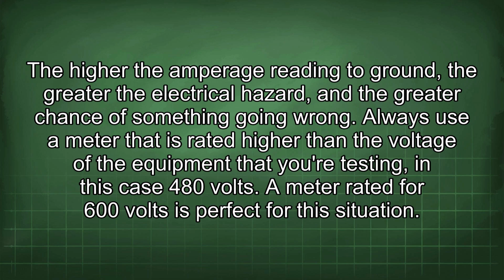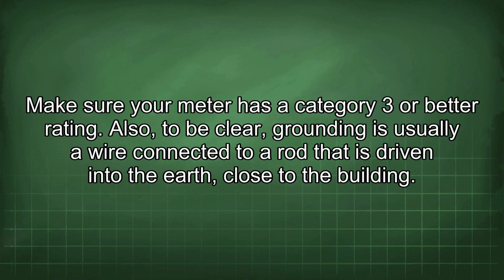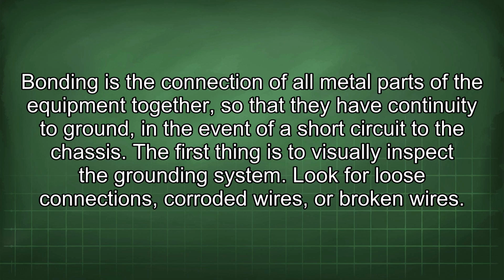Always use a meter that is rated higher than the voltage of the equipment that you're testing, in this case 480 volts. A meter rated for 600 volts is perfect for this situation. Make sure your meter has a category 3 or better rating. Also, to be clear, grounding is usually a wire connected to a rod that is driven into the earth, close to the building. Bonding is the connection of all metal parts of the equipment together, so that they have continuity to ground, in the event of a short circuit to the chassis.